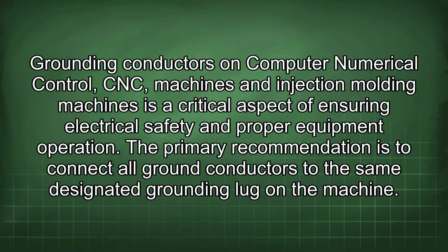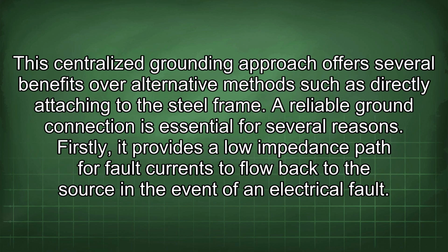Grounding conductors on computer numerical control (CNC) machines and injection molding machines is a critical aspect of ensuring electrical safety and proper equipment operation. The primary recommendation is to connect all ground conductors to the same designated grounding lug on the machine. This centralized grounding approach offers several benefits over alternative methods such as directly attaching to the steel frame.